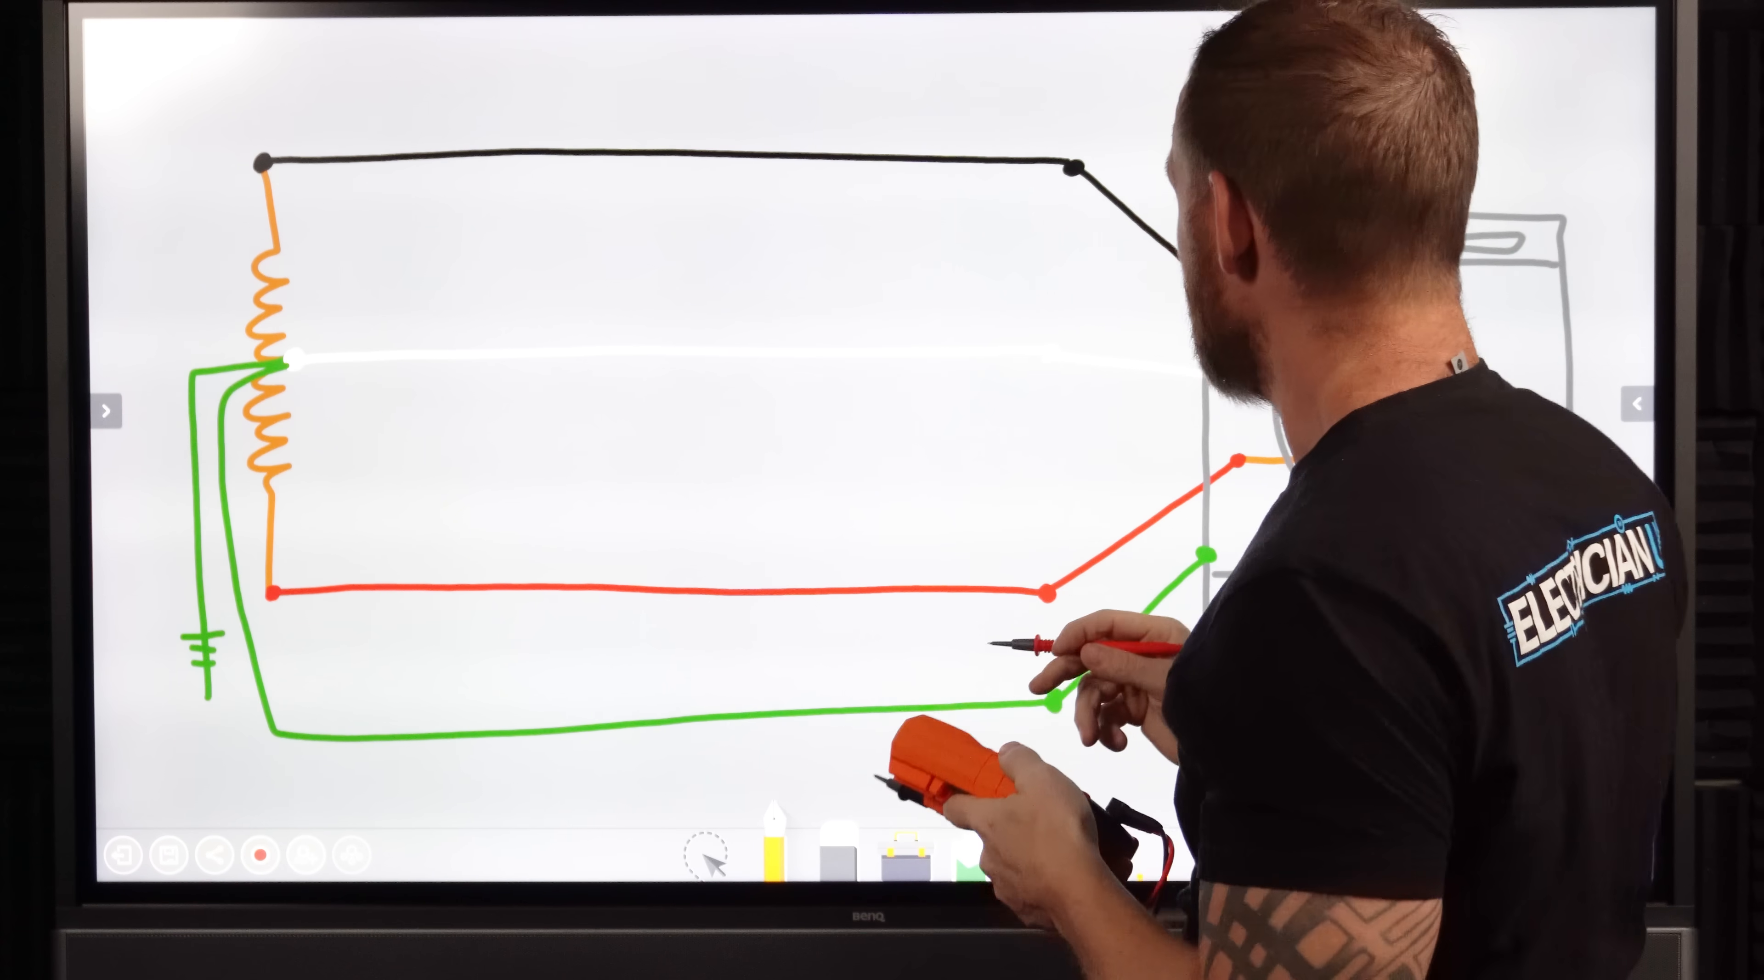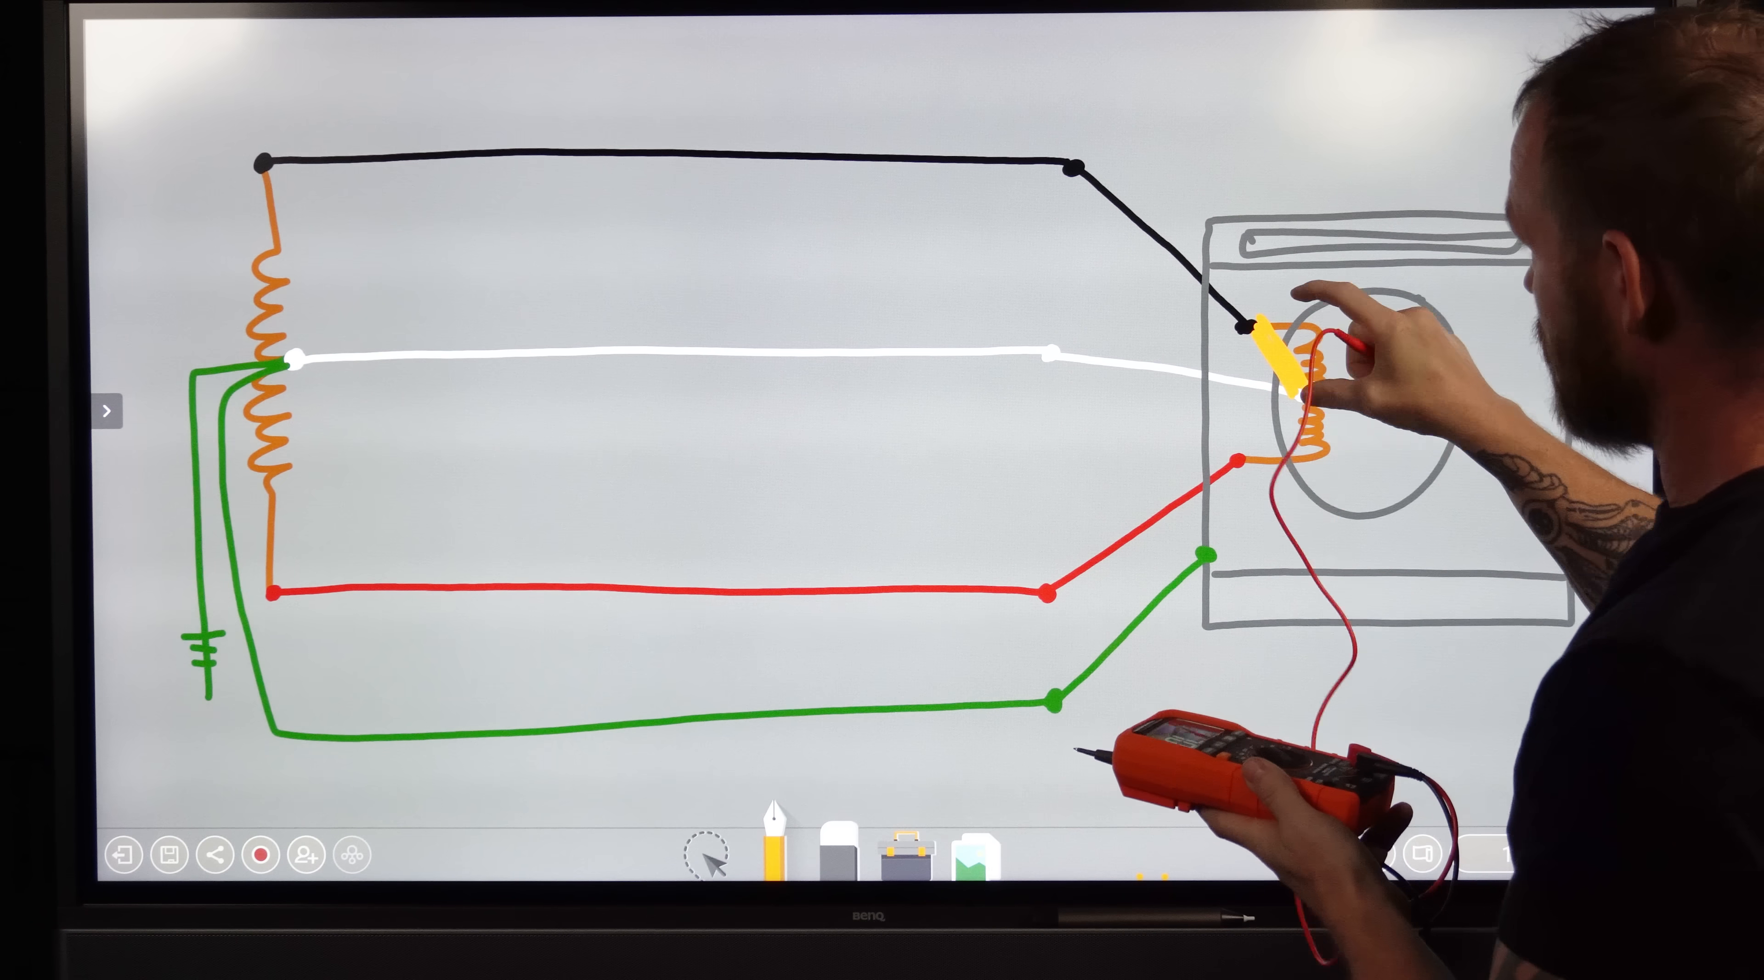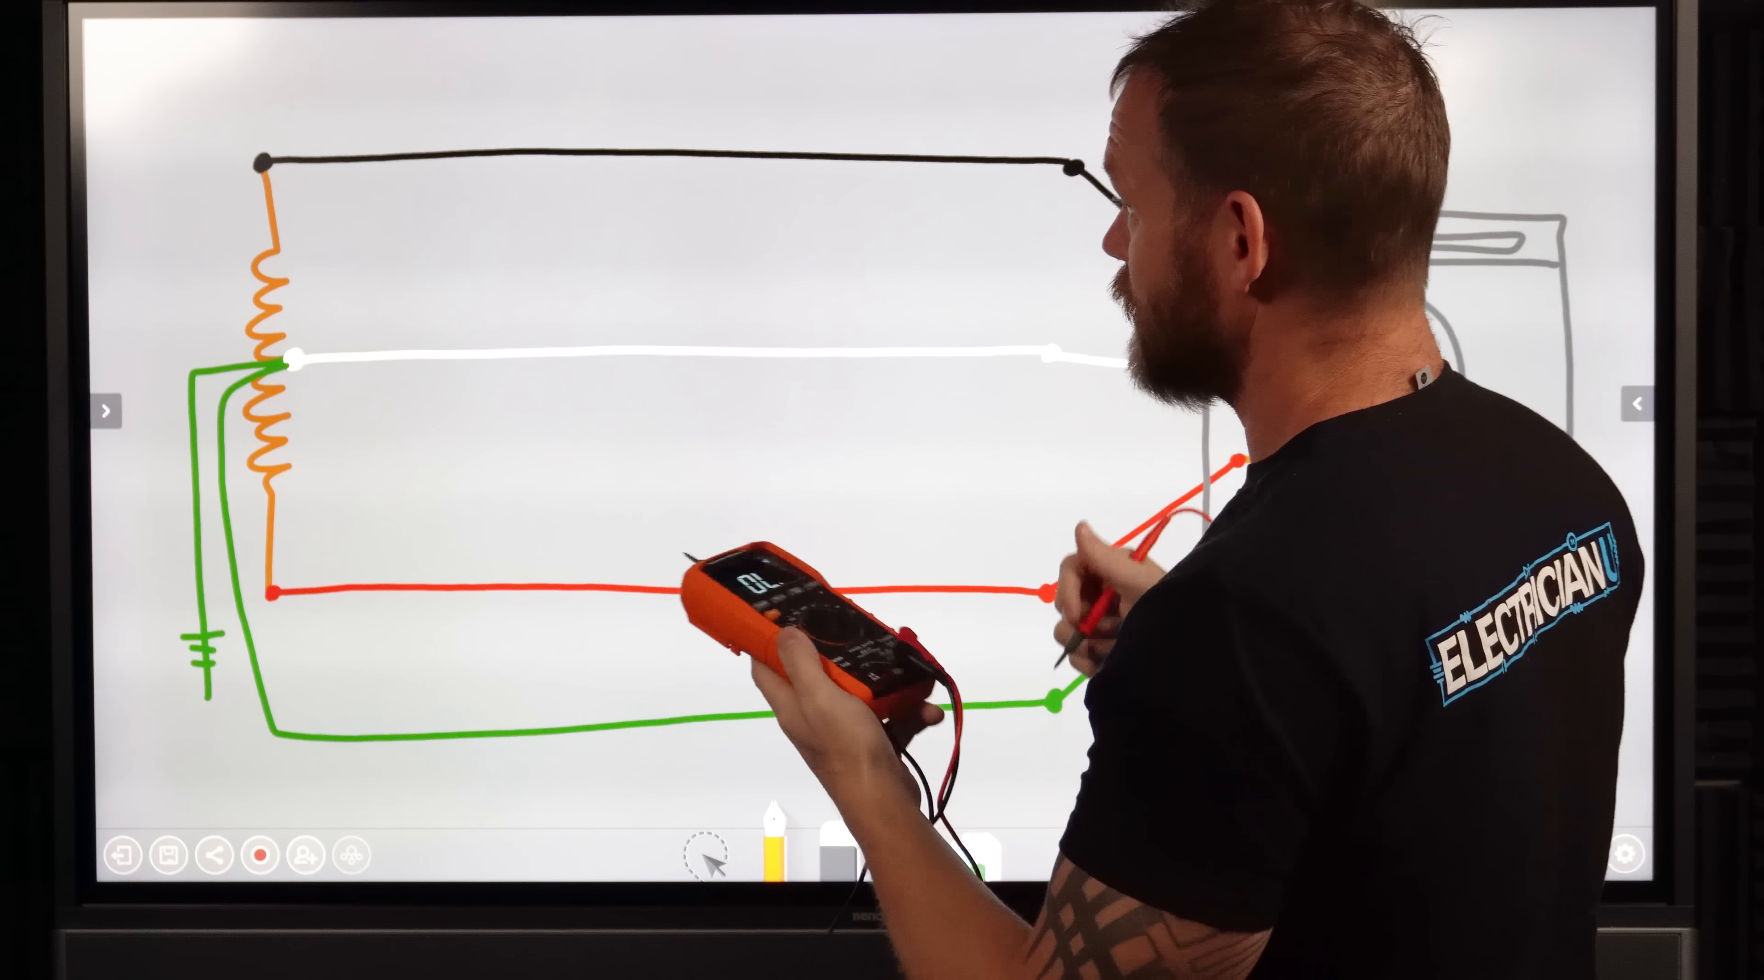You can do the same thing on the hots to check the two hots. If there's continuity between them, there shouldn't be continuity again until the load is connected going through that element. Because once you energize a load, this whole element here, this coil of wire connects to both of these. And that's what allows the motor to start working. So in that moment, while it is working, you do have a complete circuit and there is going to be continuity. But when the load is not connected, you're not going to have continuity.